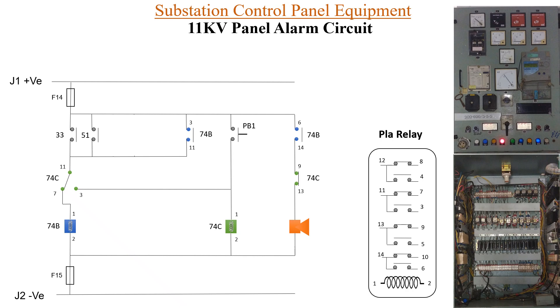In this similar fashion, you can add any number of contacts in parallel over here, as you can see. We have also taken two contacts to TB — SP9 and SP10. At SP9 and SP10, what we are doing is connecting in parallel all the feeders of the 11 kV panel board through these TB numbers. All the wiring in all the panels for the alarm and annunciation circuit are connected in parallel for each feeder. So if there is any problem in any feeder, you can check SP9 and SP10 — alarm circuit contacts are given through here only.